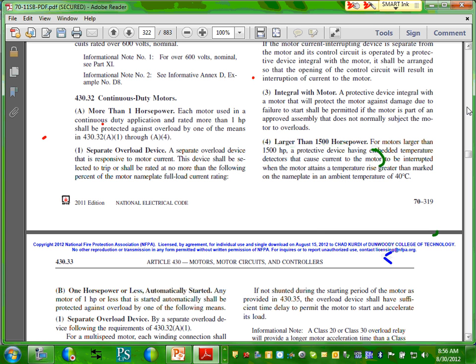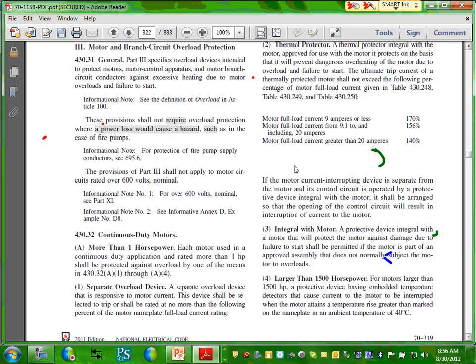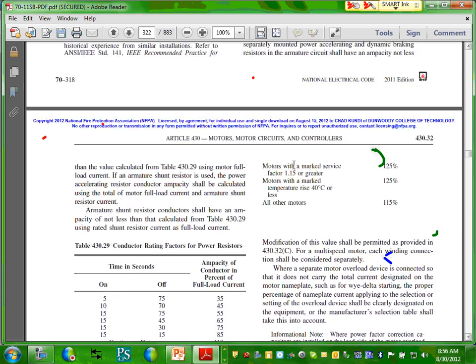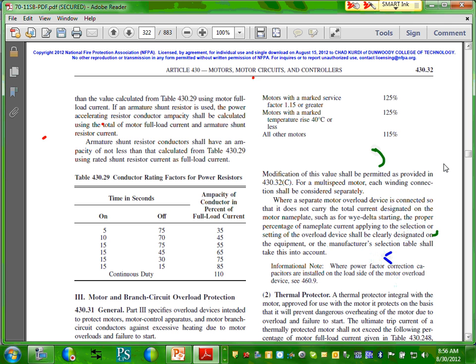This is continuous duty motors. Yep. Is it continuous duty motors? Yeah, it's a pump. It's a swimming pool pump. Continuous duty. Separate overload protection. That's typical. And so you guys, 430.32, I would like you to go right in here and highlight the following. This is where you're typically going to be for overload.